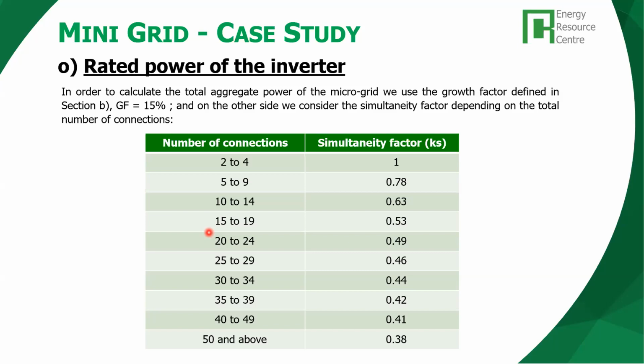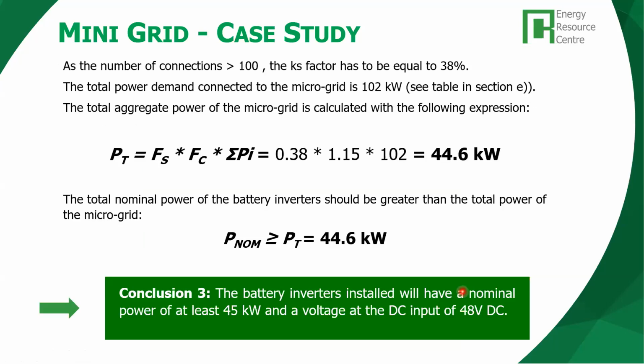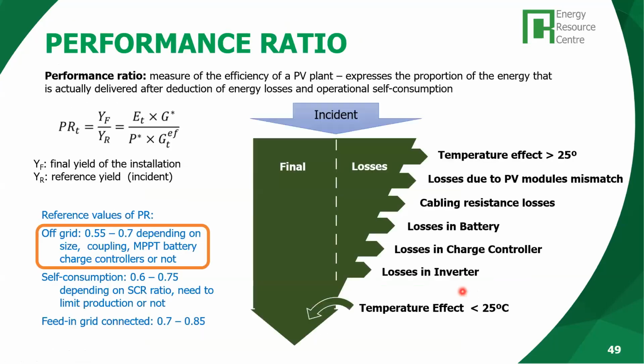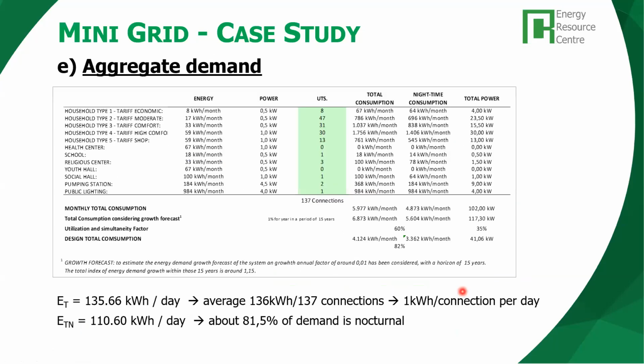So the larger the number of loads you have, the higher the probability of not using them all at the same time. So in a mini grid, with an increasing number of connections, we can have a smaller simultaneity factor. And when we are above 50 connections for a mini grid, typically we start considering simultaneity factors below 40%. So we use this simultaneity factor to downsize our gross power demand in the mini grid. Remember, this comes from our table of the demand here.